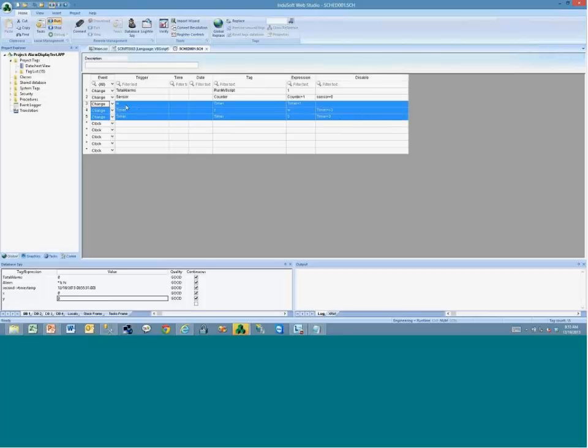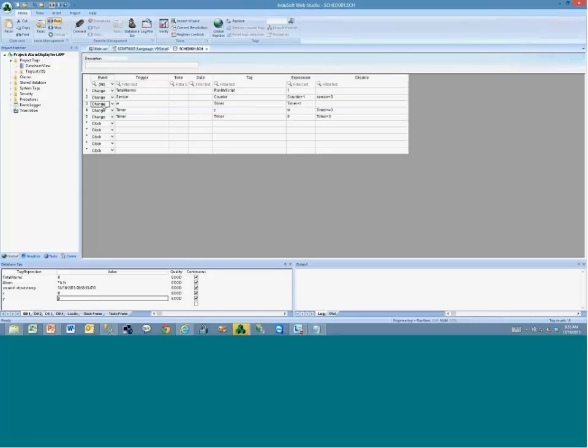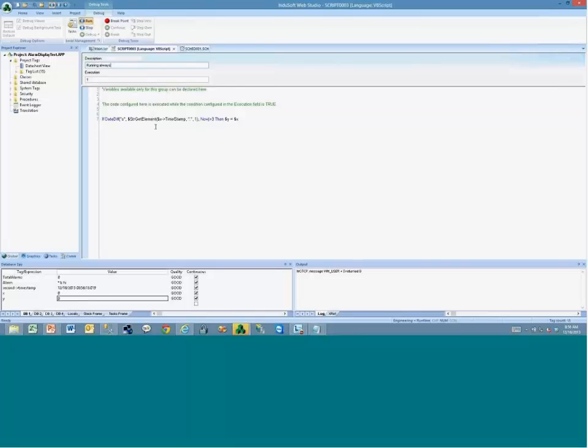When W is different, clock, here has to be clock. I keep incrementing timer while W is different from Z. So if W is equal to Z, nothing happens, everything's cool. If W changes, then every second, timer keeps incrementing. When timer reaches a limit, then the value of W goes to Z, and when this limit is reached, I reset timer again. So 3 lines, you don't have to write any scripts. I particularly find this way simpler, but either way is possible.